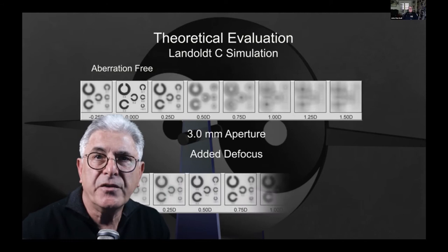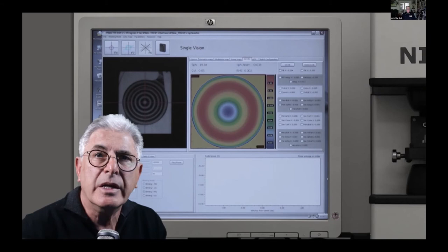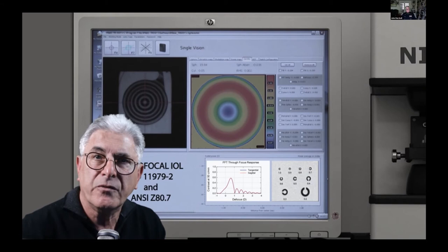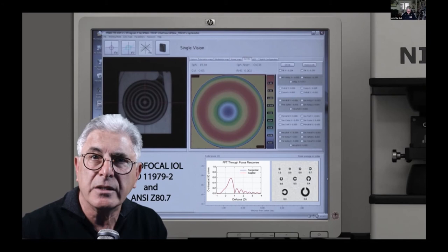The aspheric anterior surface has a unique optic design, with an inner optic zone that utilizes 4th and 6th order high-order positive spherical aberration, blending in an apodized fashion with the peripheral zone to extend depth of field without compromising visual acuity under low light conditions. This lens has been designed to meet the ANSI and ISO standards for a high quality monofocal intraocular lens.